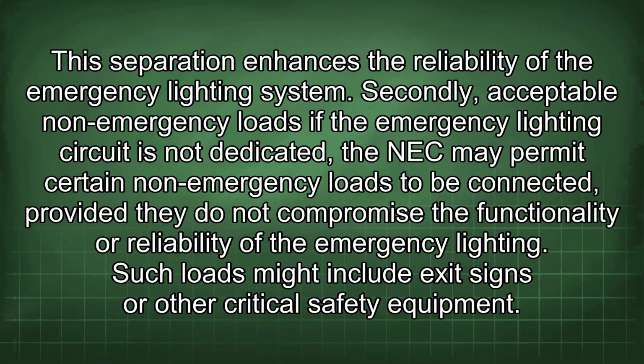Secondly, acceptable non-emergency loads. If the emergency lighting circuit is not dedicated, the NEC may permit certain non-emergency loads to be connected, provided they do not compromise the functionality or reliability of the emergency lighting. Such loads might include exit signs or other critical safety equipment.